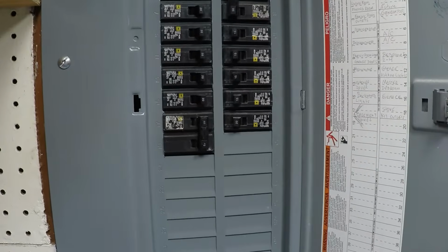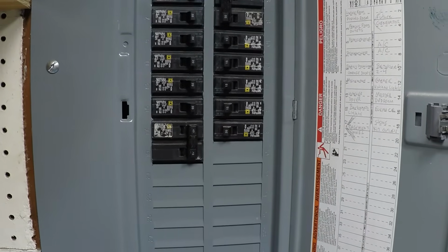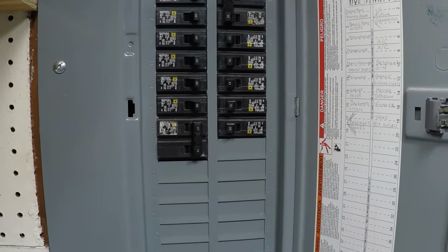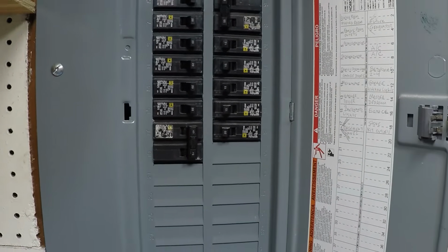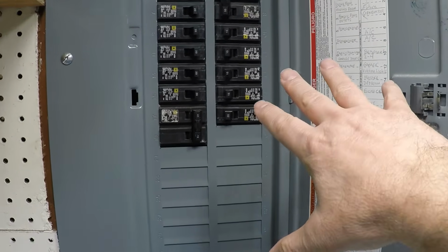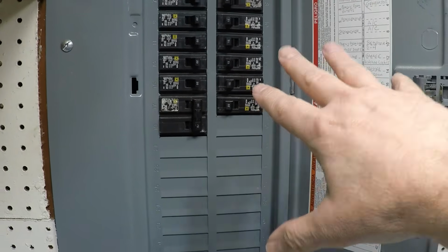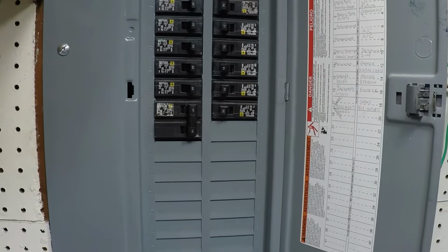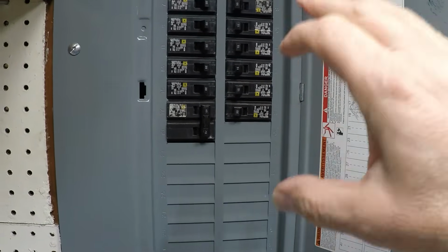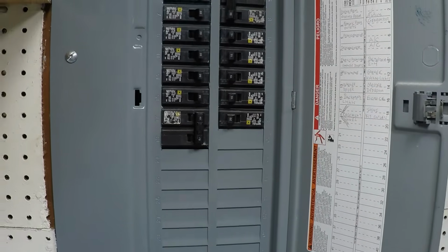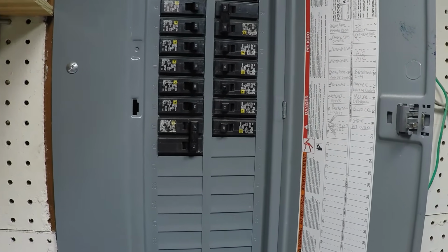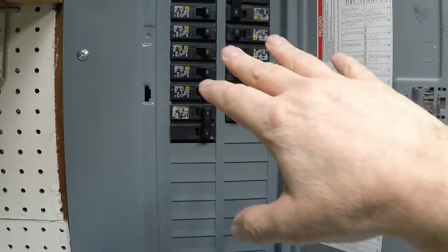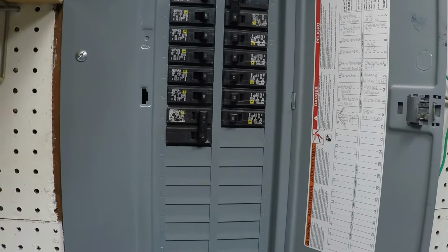I'll show you that with the sub panel downstairs with the GFCI breaker; it's going to float in the middle. Now, if you reset it and then try the appliance or the lights or whatever in your house had just recently shut off and the power's still not on, then it's something other than your breaker. Then we've got a wiring situation.